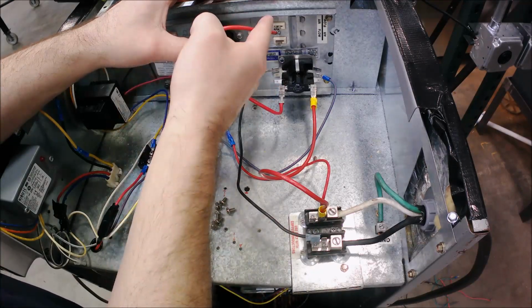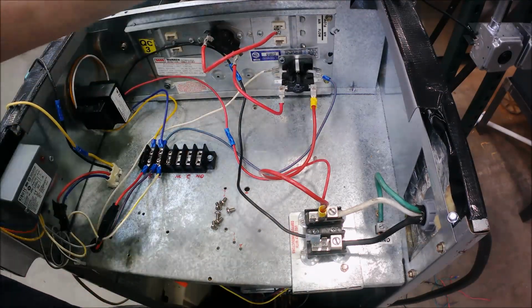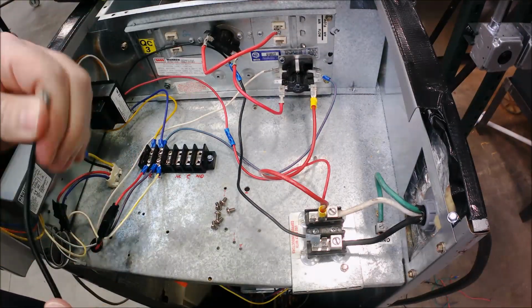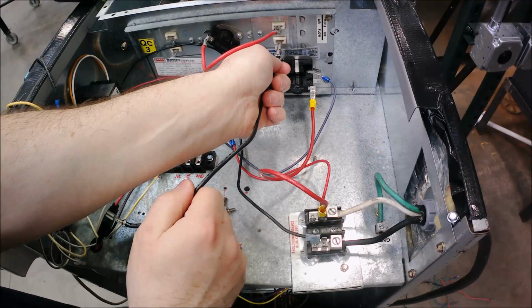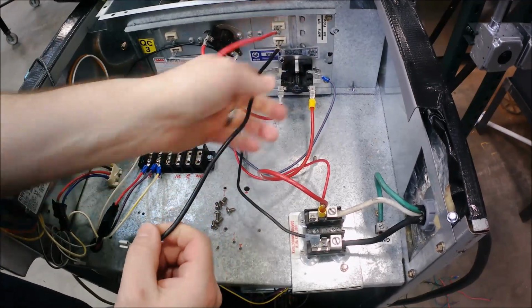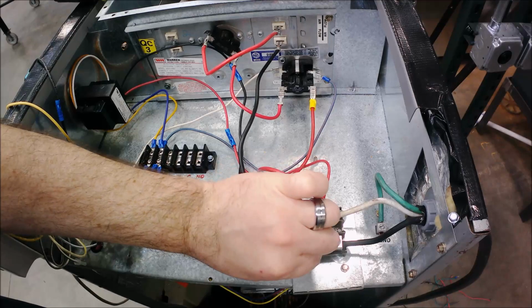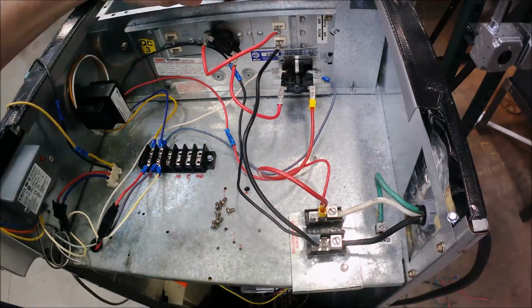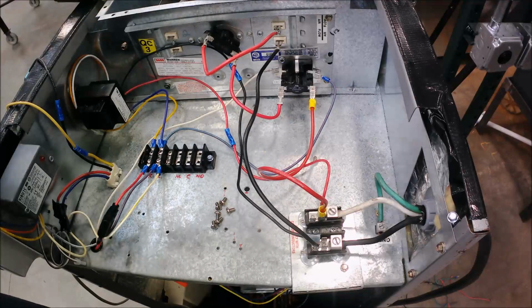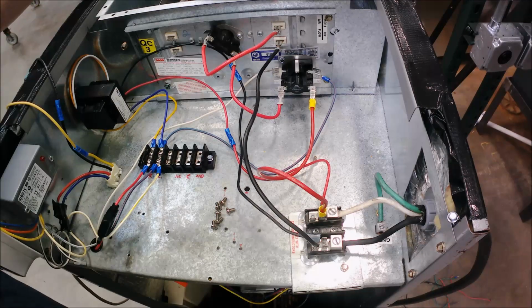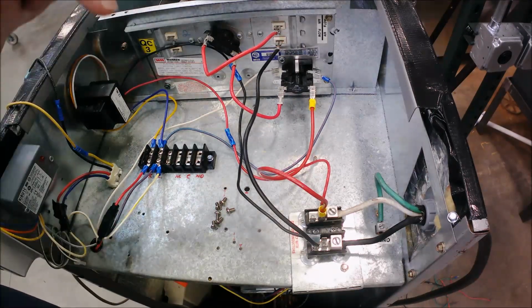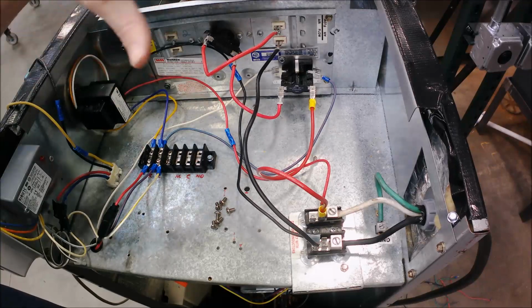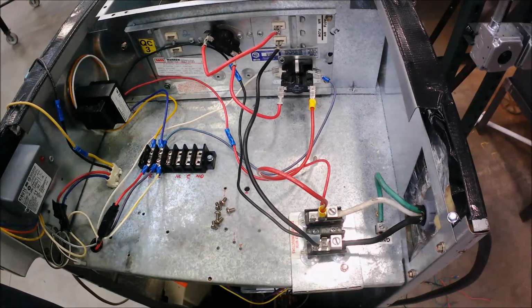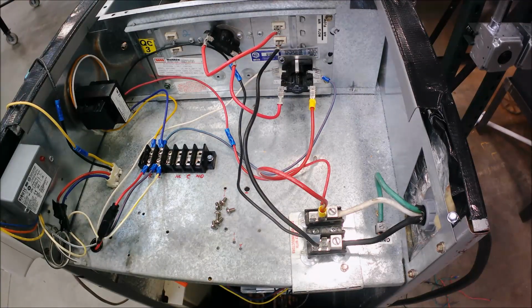Power, control, our load. So now we have to return back to the other side of power. So we're going to take and change colors here. It's black. And we're going to go right there and return it back to the terminal block. And now that one heater is done. I've got the yellow wires over here to distinguish the second heater in case we were following it, but you can go back and dig up a video on that one. I've already done that. So our transformer's done, our high voltage on our sequencer, and the electric heater, like that whole circuit's done. Now we have to look at the rib relay and the fan.